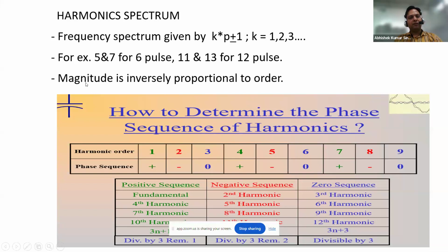And the most important thing is that the magnitude is inversely proportional to the order. So the point is, the higher the order, the lower the magnitude of the harmonics. It means the lower order harmonics are more dangerous as compared to higher order harmonics. This is very important: lower order harmonics like third, fifth, and seventh have high magnitude as compared to the 13th order, 17th order, or 19th order. That's why we always try to control the third, fifth, and seventh. These are the most common, as you all have heard. I believe most of us are industry experts, so definitely you have heard about it.